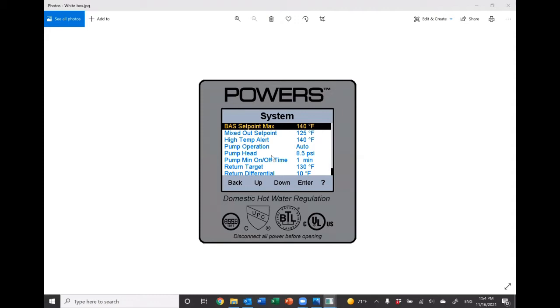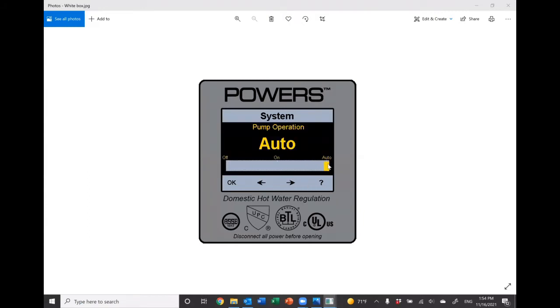Pump operation, you just go in, hit enter, it's either on, off, or auto. Auto is going to shut the recirc pump down whenever the temperature is pretty much what it went out at, so it doesn't need to recirc water. And once that sensor cools, it'll say, okay, hey, time to kick back on, and you'll set a minimum on and off time for that too if you choose to. Or you can just have it off, have it controlled separately by power or by an aquastat, or you can have it just always on run, which is my preferred setup on it. But each case is different.